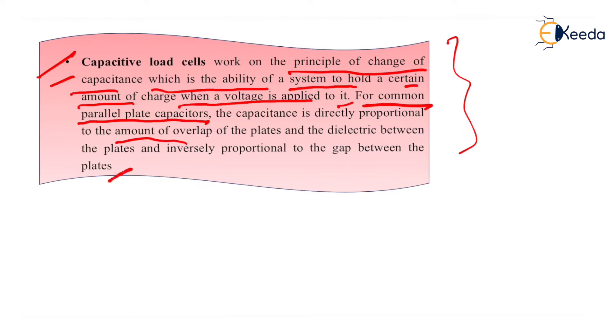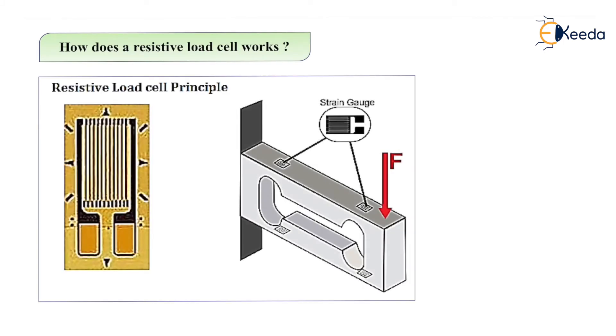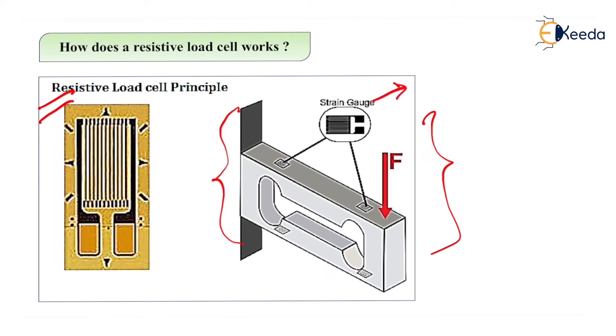We have now seen both resistive and capacitive types of load cells. Looking at the diagram of the resistive load cell, we can see its internal structure. There are strain gauges connected to the load cell body, forming a Wheatstone bridge configuration. These strain gauges are responsible for the change in resistance.